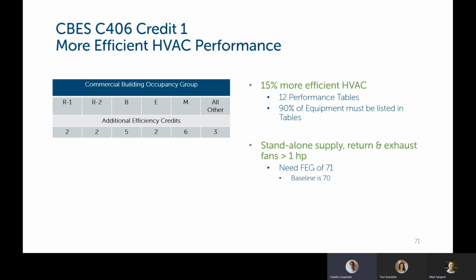So the first credit is for more efficient HVAC performance, and you would need to have 15% more efficient HVAC equipment for all of your equipment that is listed in the 12 performance tables of the code, including heat pumps, boilers, chillers, any of that equipment. And 90% of your equipment in the building must be the types of equipment that are listed in those tables. So if you hit that requirement, as you can see in the chart here, you find your building occupancy type, and then down below that are the number of credits that you could get for doing that. So you need to get 6 credits. For the mercantile, the sales type building, you could get all your credits just for doing this one type of additional efficiency package.